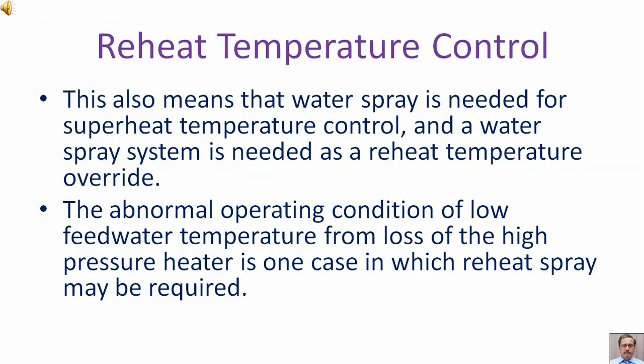Reheat temperature control. This also means that water spray is needed for superheat temperature control, and a water spray system is needed as a reheat temperature override. The abnormal operating condition of low feed water temperature from loss of the high pressure heater is one case in which reheat spray may be required.